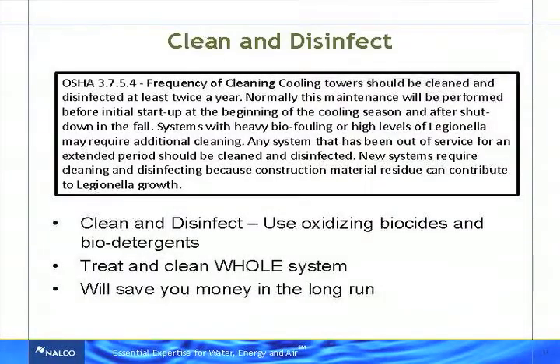Fifth and final thing is clean and disinfect. Mike already mentioned the OSHA regulations 3754 requires you to clean your cooling tower twice a year. What they say is you should clean it on shutdown and clean it on startup. I think that you could probably just do a very thorough cleaning on shutdown and help out with a lot of those regulations. But they say clean and disinfect.